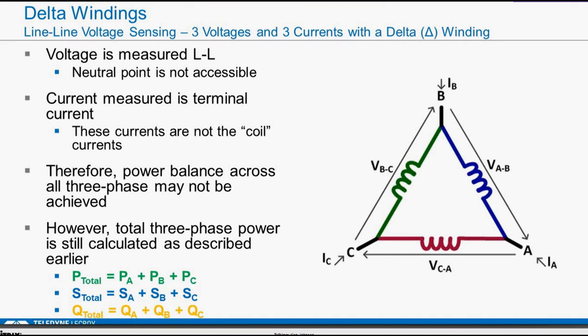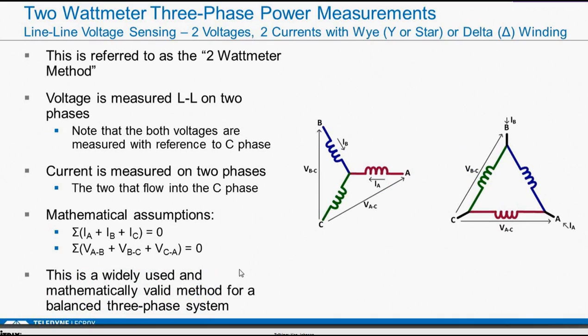Okay, so if you have a delta winding, again, by definition, you are sensing line-to-line voltage, and you have a terminal current. So these currents are not the coil currents. We know the current coming into the terminal. The power balance across all three phases may not be achieved. You might have an imbalanced phase. You might want to use a 2-wattmeter method in this case. But in any case, the total three-phase power calculation is what we described earlier, the summation of the phases.